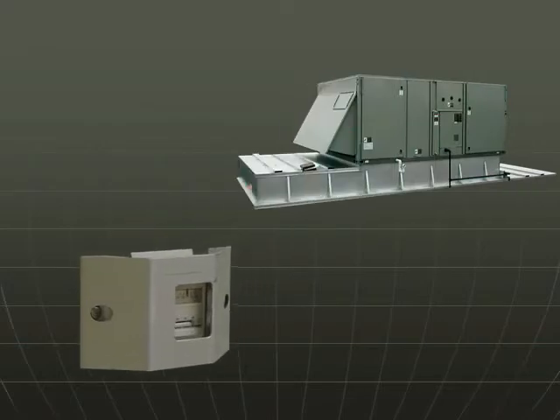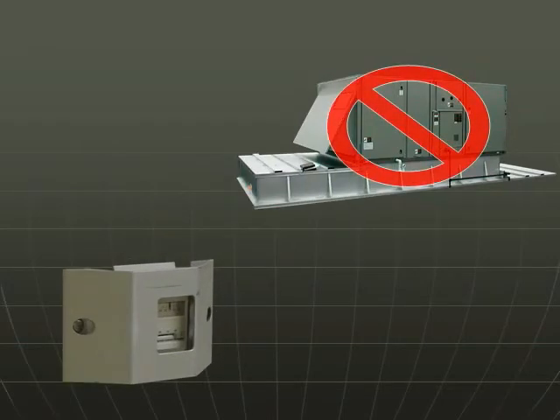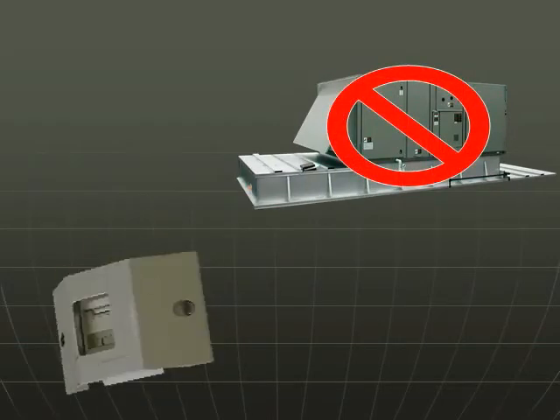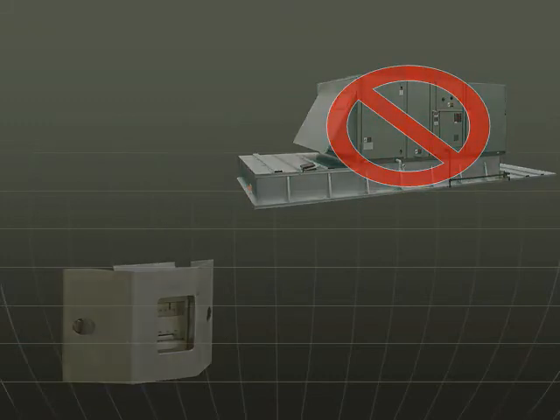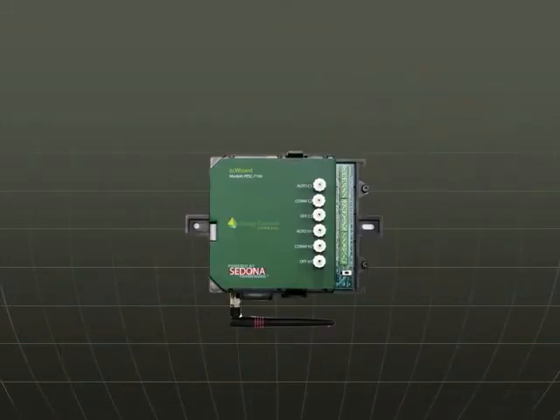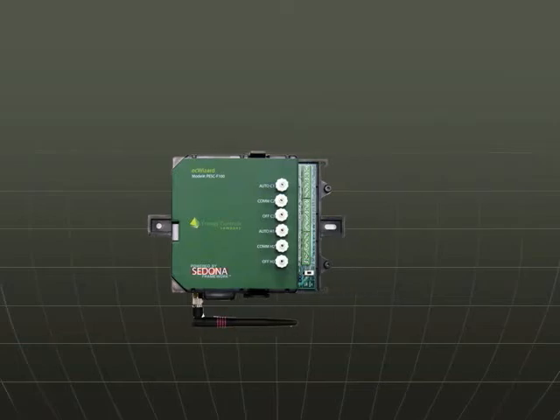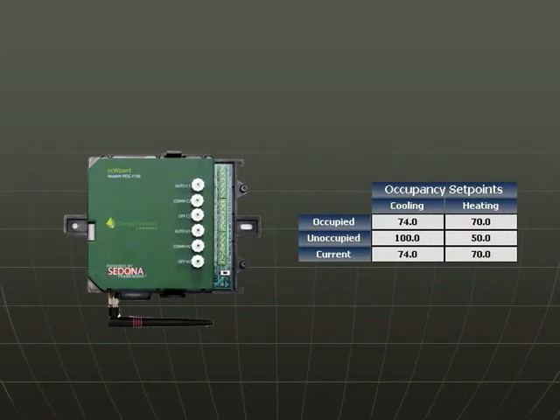adjustments. When the main heating or cooling system malfunctions, the first thing that happens is the pneumatic thermostat usually gets out of adjustment. The ecWizard eliminates this excessive energy waste and maintains the comfort level after the main HVAC system is running properly, by having set point limitations within the software.